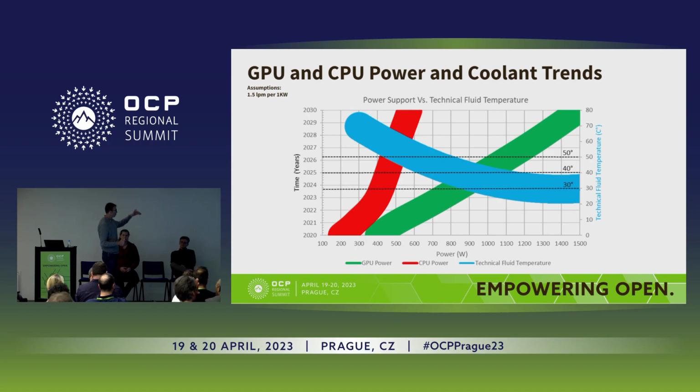And Chris talked about packaging. This is with more aggressive packaging than we have today. We're still having a requirement that, for longevity, for an AI workload, and I want to be specific here, if you're doing a bunch of virtualized workloads, maybe you can stay in a liquid-cooled, higher water temperature. But we're seeing a huge propensity for these scale-up AI models, and those are driving very high power at the GPU and interconnect. And those are going to drive the requirements for a lot lower water temperature.